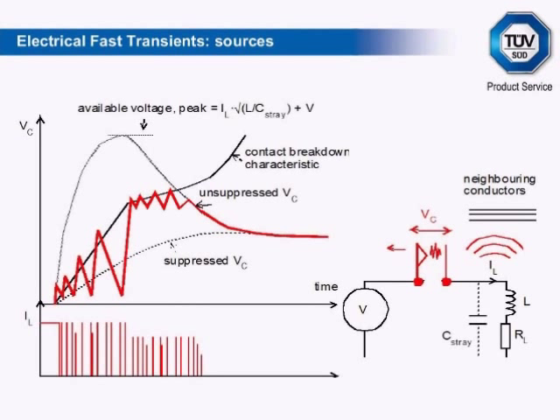The electrical fast transient bursts test subjects the EUT to bursts of transients that test its immunity to environmental disturbances caused mainly by local power switching operations. The transients are called fast to distinguish them from lower frequency surges caused by distant disturbances outside the immediate environment.